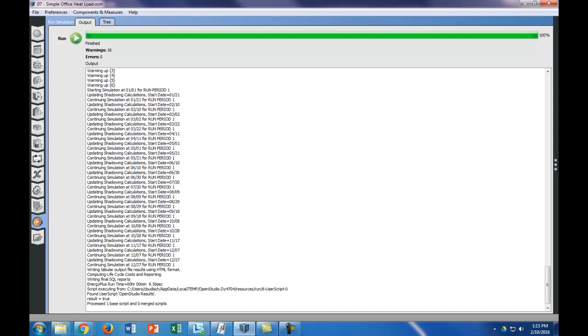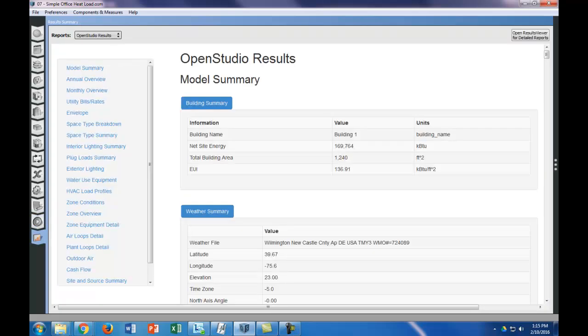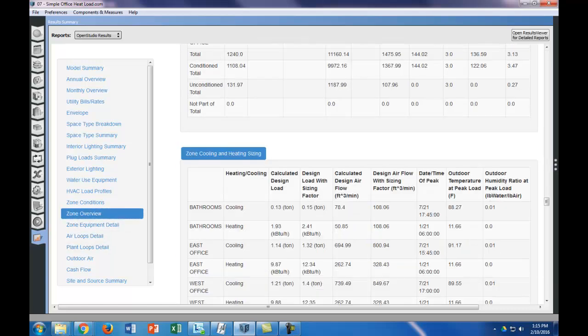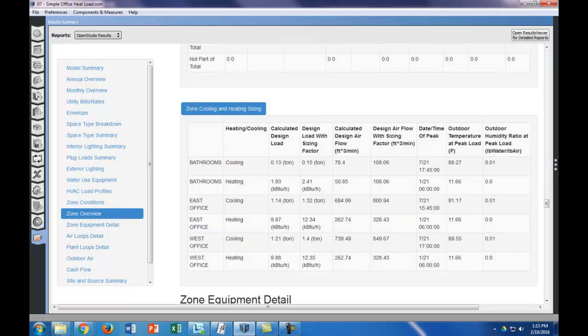Okay, so now let's go back to our output results, and go back down to the zone overview, and now we have the zone cooling and heating size. So basically, if you wanted the full heating load, you would add up, without adding in the safety factor, you'd add up the 1.93, plus the 9.87, plus the 9.88 for the heating. And for the cooling, you would add up the 0.13 tons, 1.14 tons, and 1.21 tons. And then you can compare that with the heating and cooling load you got by hand.